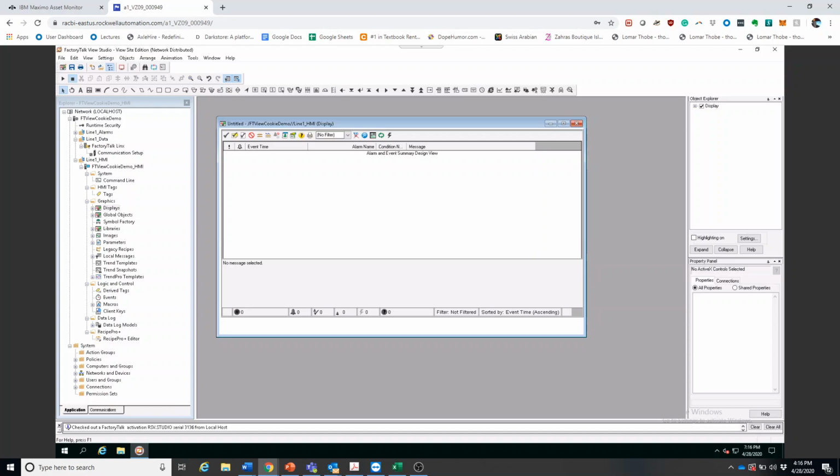An analog alarm, also known as the ALMA instruction, can be configured to monitor for two types of alarm condition: level and rate of change. A level alarm monitors an input for alarm conditions that go in alarm when the input value goes above or below predefined limits. When defining a new level alarm, you can configure up to 4 alarm level conditions, each sometimes called a threshold, with a severity of alarm supported, such as high high, high, low, or low low.